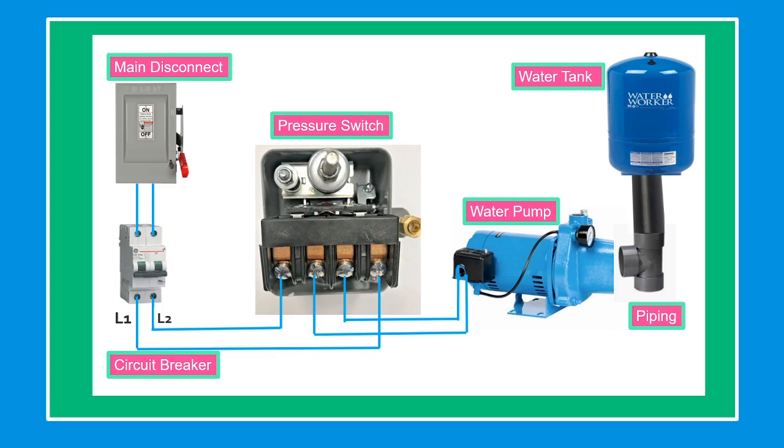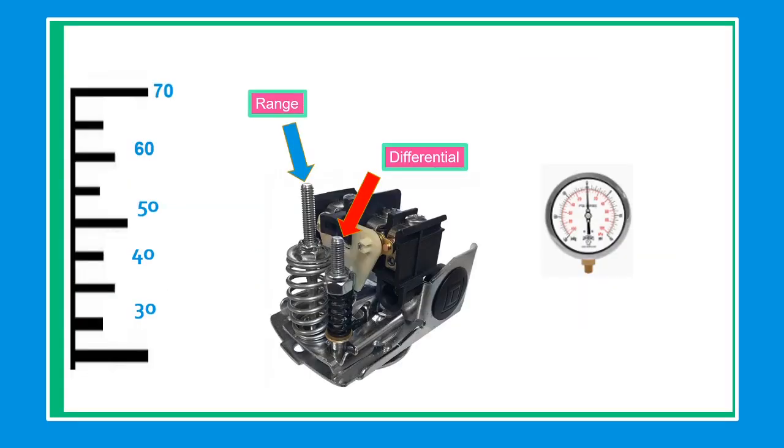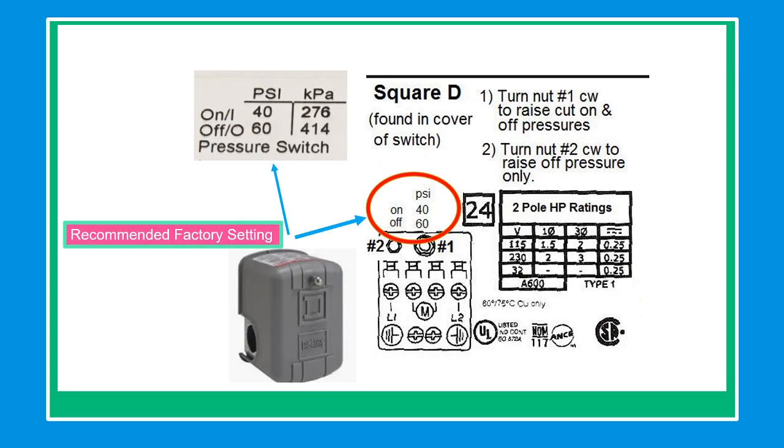We have two pressure type adjustments: the center is your range and at the side is your differential. You can find factory preset setting adjustments inside the cover or in the box. For submersible pump, 40 to 60 psi, and for jet pump with smaller horsepower that can be used at home or irrigation, mostly run 20 to 40 psi or 30 to 50 psi.